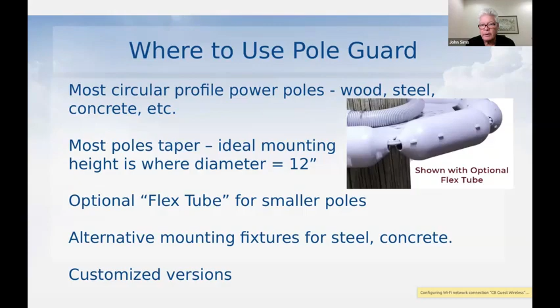The ideal mounting height is where the pole diameter is 12 inches, or 38 inches in circumference. We sell an optional flex tube, a simple piece of conduit that wraps around the pole. If you have a smaller pole, say 9 or 10 inches, you'd have a gap of an inch or two around the pole guard plates, which wouldn't necessarily stop a squirrel or a snake. The flex tube, as you can see in the close-up picture, will stop it.